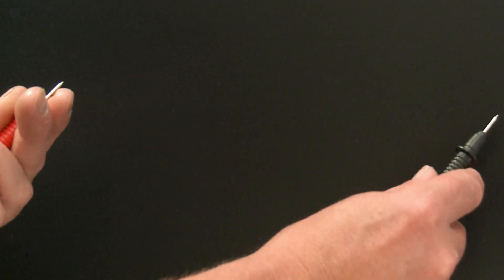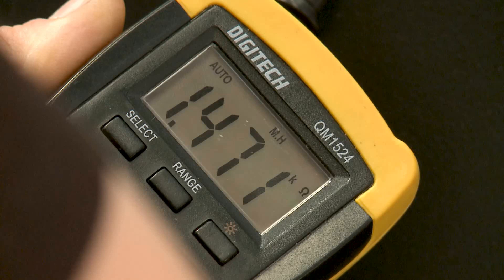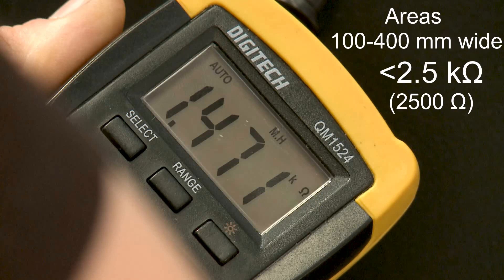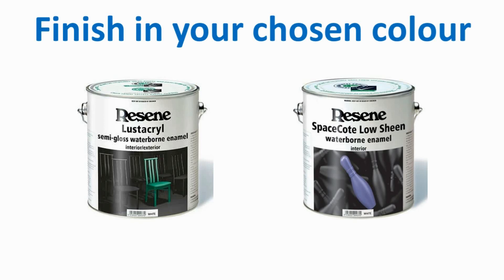If using pointed probes, press the probe edge — not the point — onto the coating. All measurements should be less than 1800 ohms for areas wider than 400mm, and less than 2500 ohms for areas between 100 and 400mm wide. Finally, finish the job with a Resene SpaceCote or Lustacryl.